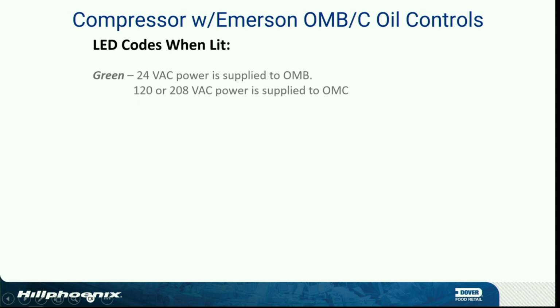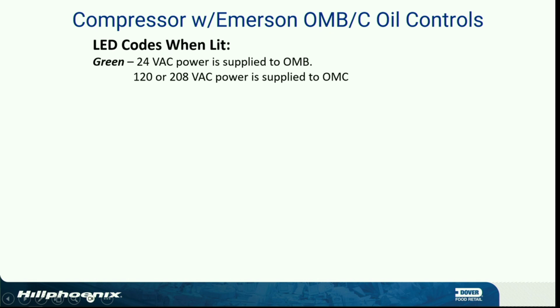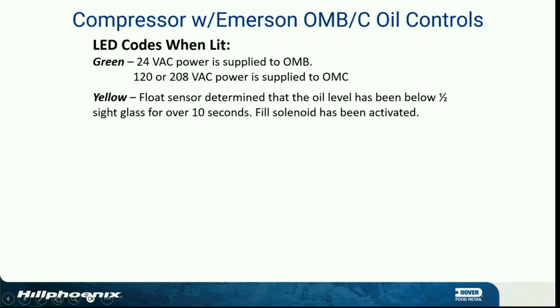Compressor with Emerson, compressor with Copeland OMB and OMC oil controls. LED codes when lit. Green: 24-volt power is supplied to the OMB, and 120 volt or 208 power is supplied to the OMC. Yellow: the float sensor determined that the oil level has been below half, 40%, for about 10 seconds. The fill solenoid has been activated, and it'll be activated for anybody remember how long? A maximum of 2 minutes, and then it's going to lock out and trip.